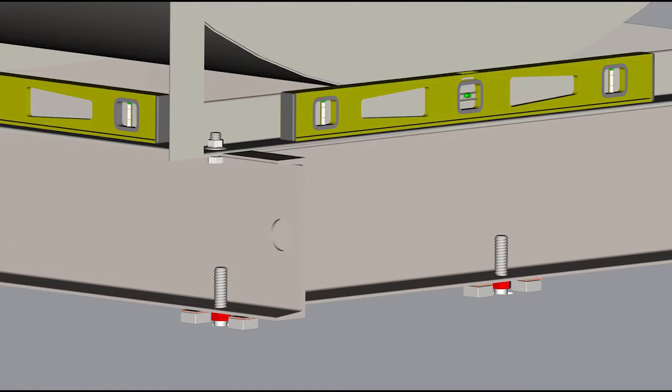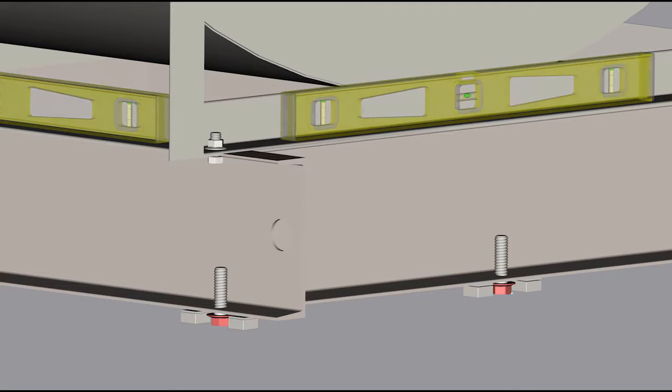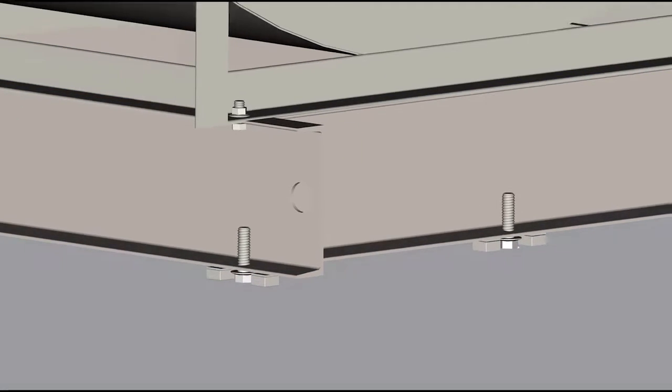The fan not only needs a foundation with adequate mass and stiffness, it needs clamping force exerted on the foundation through the shims and foundation bolts.